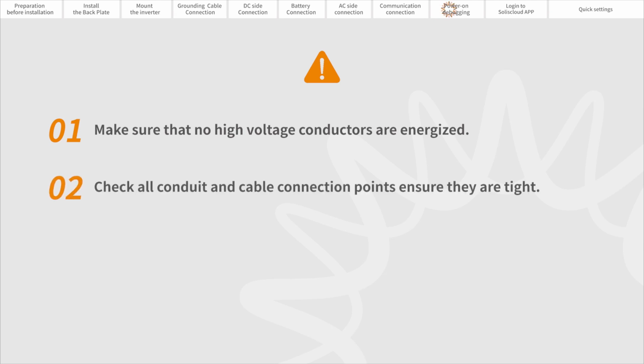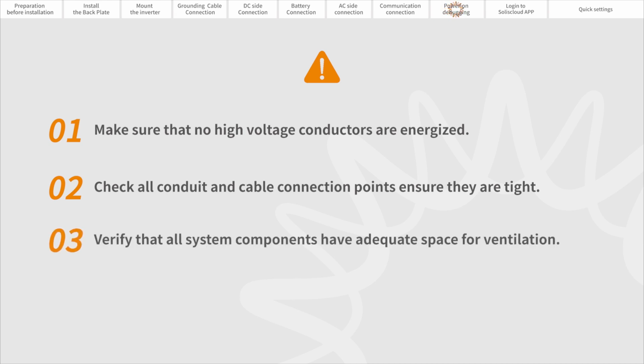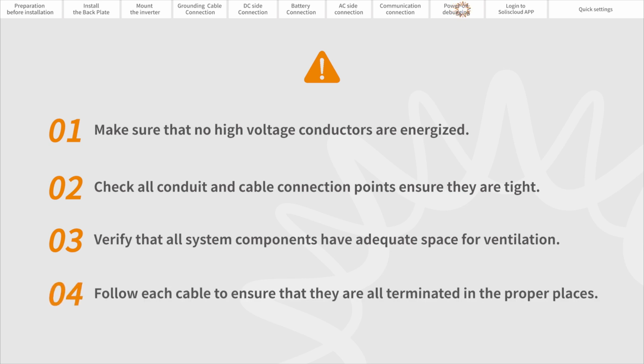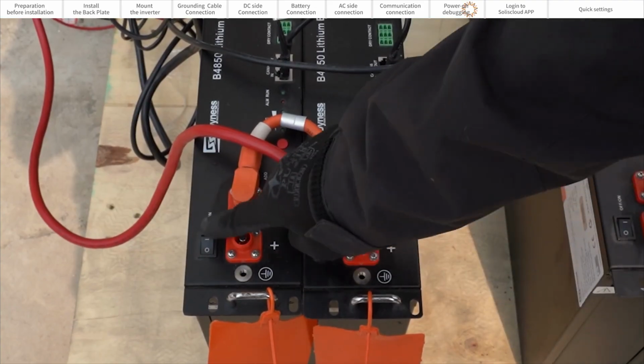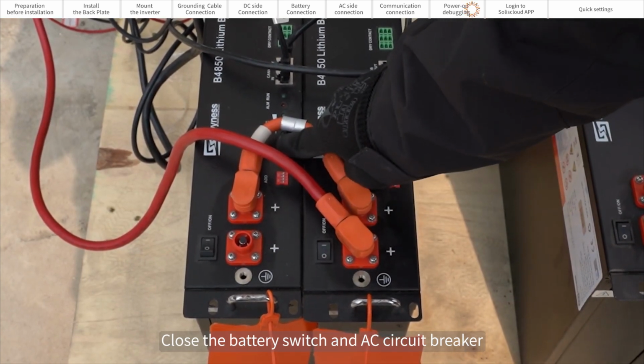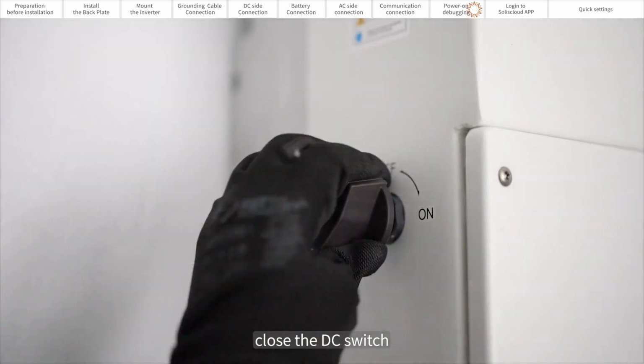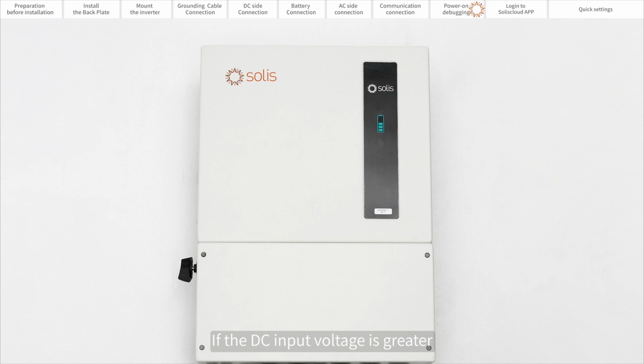Check all conduit and cable connection points and ensure they are tight. Verify that all system components have adequate space for ventilation. Follow each cable to ensure that they are all terminated in their proper places. Close the battery switch and the AC circuit breaker. Close the DC switch. If the DC input voltage is greater than the startup voltage, the inverter will start.